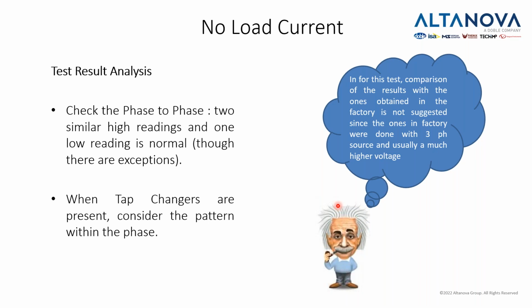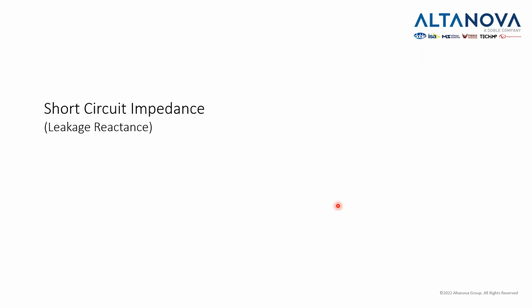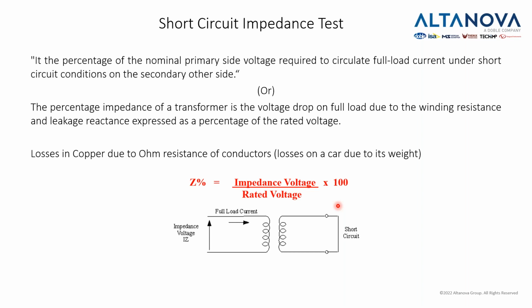We need to compare and see if, let's say, the results we did today are different from the results we did last time when we did the test, and we also compare the phases. Short circuit impedance is the percentage of the nominal primary side voltage required to circulate full load current under short circuit conditions of the secondary side, or the percentage impedance of the transformer that is a full load drop due to the winding resistance and leakage reactance expressed as a percentage of the rated voltage.